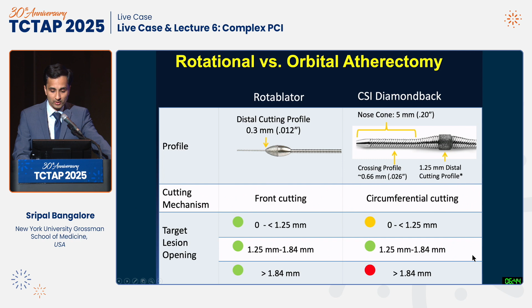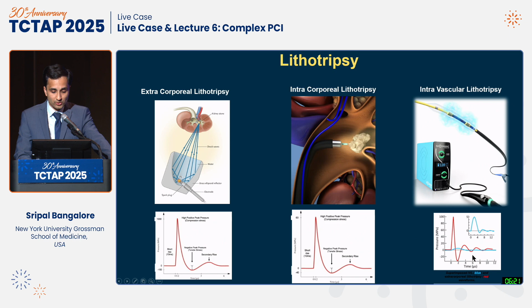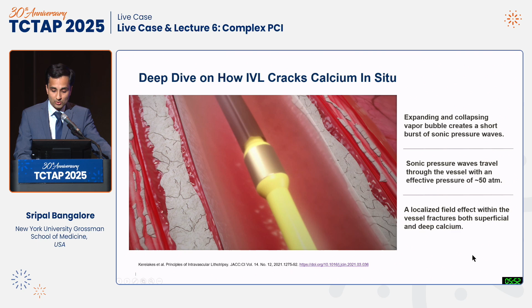What about intravascular lithotripsy? The technology is based on lithotripsy used for kidney stones. The extracorporeal lithotripsy uses very high pressure. If you move away from that to intracorporeal lithotripsy, the pressure required is less. And if you use intravascular lithotripsy, the pressure is even less. This cartoon shows how IVL cracks calcium in situ. There are emitters which create an expanding and collapsing vapor bubble, and it creates short bursts of sonic pressure waves. The sonic pressure waves travel through the vessel with an effective pressure of close to 50 atmospheres. This localized field effect within the vessel fractures both superficial and deep calcification.